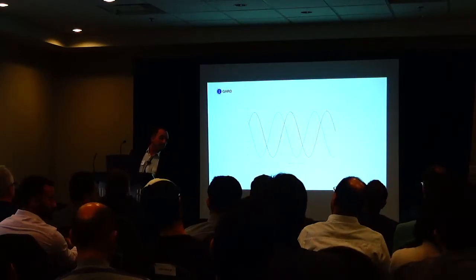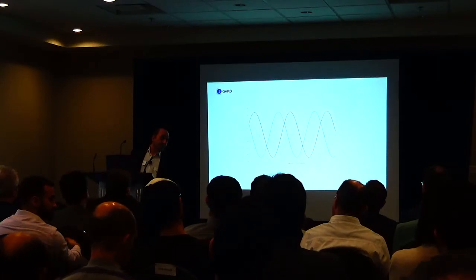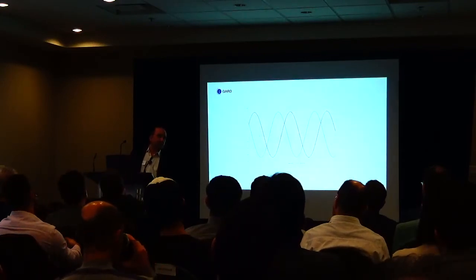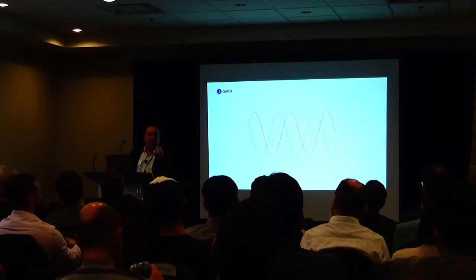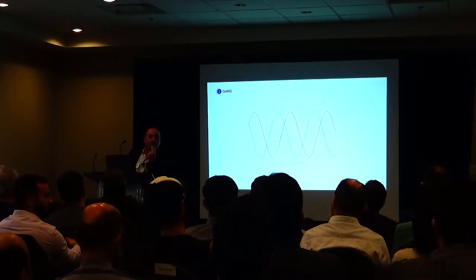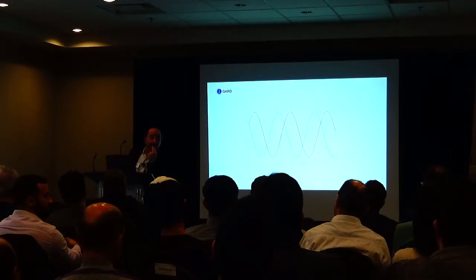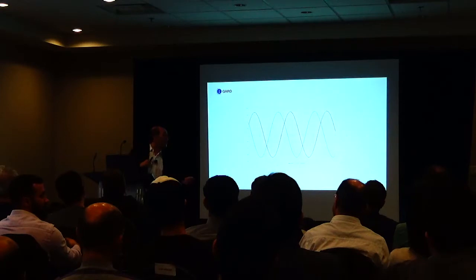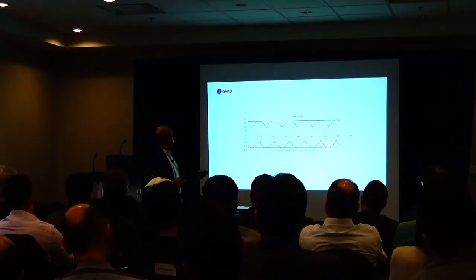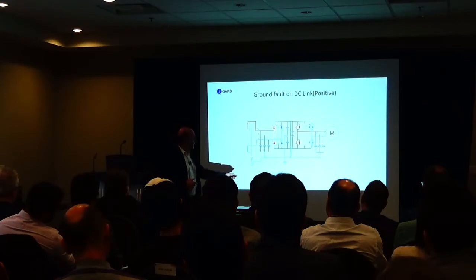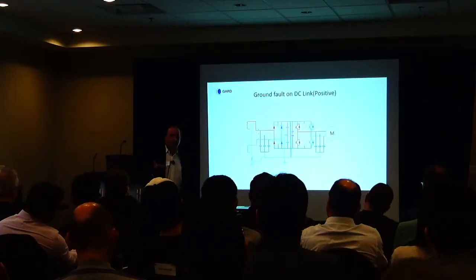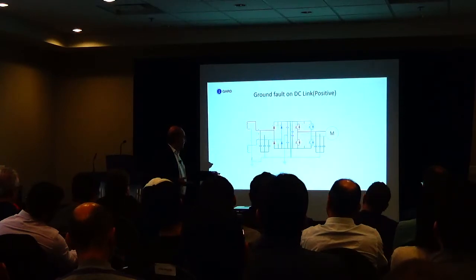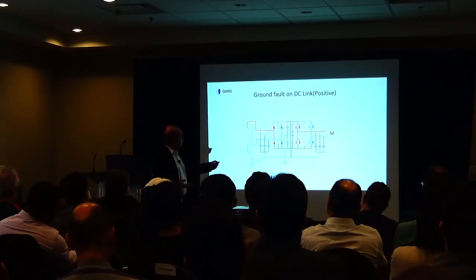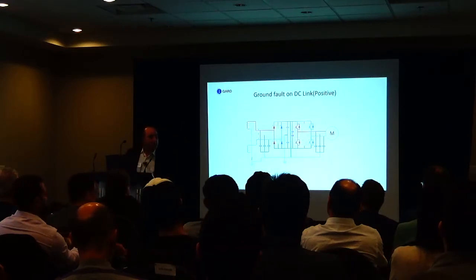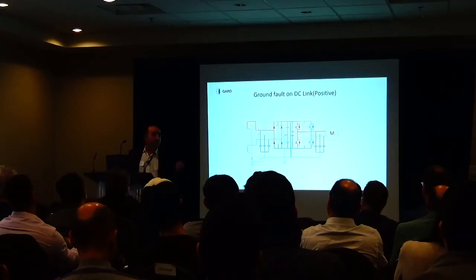But DC bus is not insulated from the ground? It is insulated from the ground. What? But when a fault happens on the DC bus, how can it come back to the source? How does it come back to the source? If you have a ground fault on the DC bus, that means your connection here, you have this point here, the positive bus is connected to ground. That's what a ground fault would be on a DC bus, right? So now you complete your circuit. It goes this way, and it goes either here, here, or here, back to the DC bus. And you complete the circuit. You're making a ground fault to each phase equally. On the DC bus, yeah.